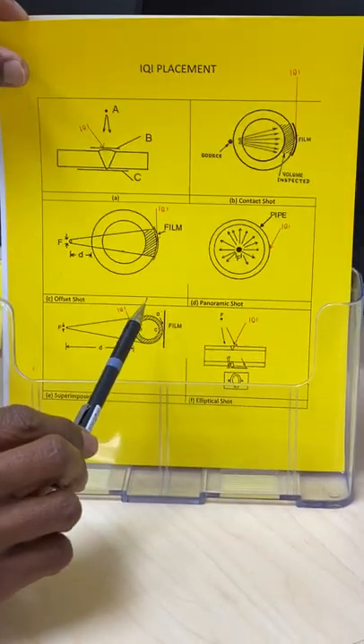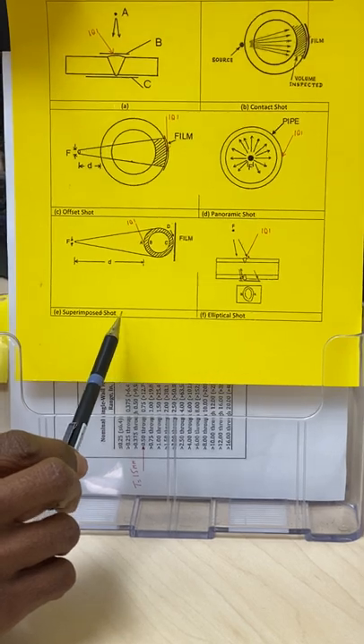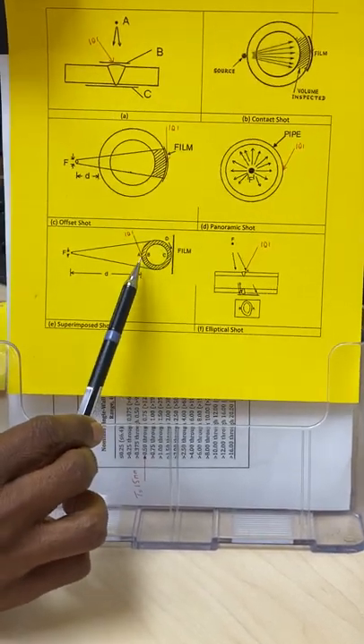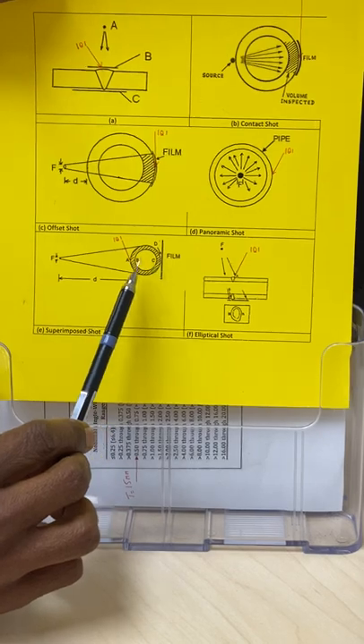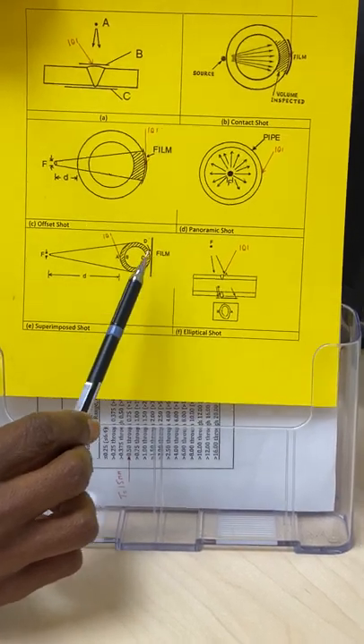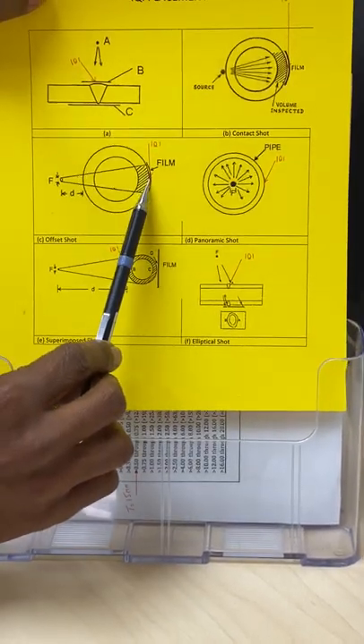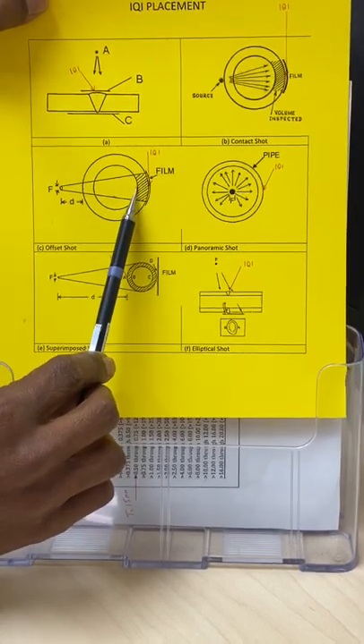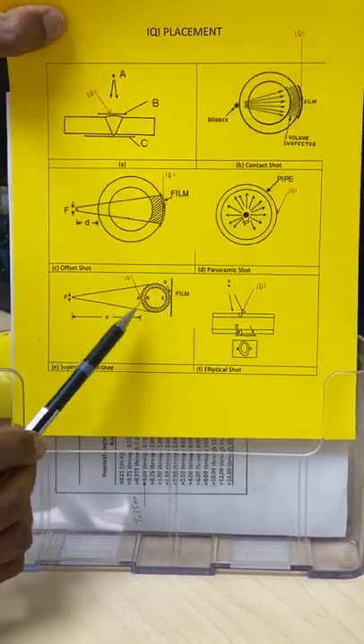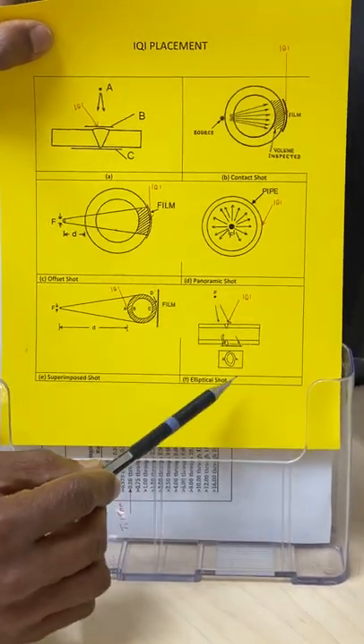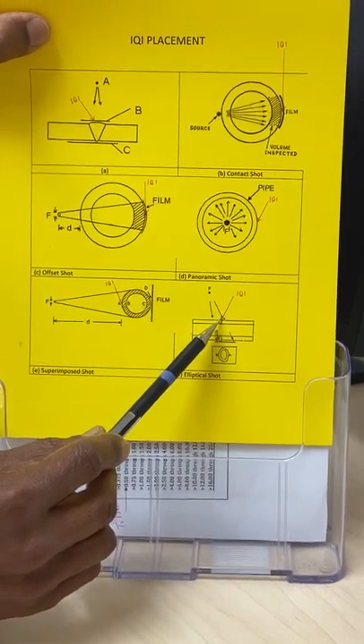For the double wall exposure double wall viewing superimpose shot, the IQI is placed on the source side, because we are viewing both thicknesses and the source side is accessible. For double wall exposure double wall viewing elliptical shot, the IQI also goes on the source side. Remember: if the source side is accessible, you must place the IQI on the source side.